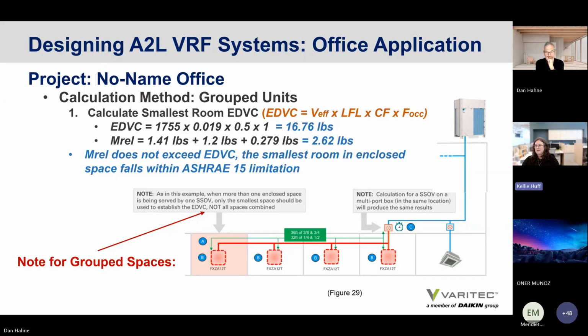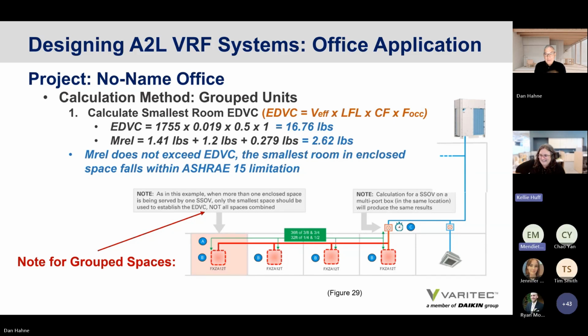Okay. And what estimate does Daikin have for MREL roughly in, say, a 4-ton fan coil to a branch box at like 50 feet one-way length? Well, that's pretty detailed. Based on just some of the example problems we've done, you're looking at anywhere between 1 and 2 pounds. But again, that's a big time guess on my part.